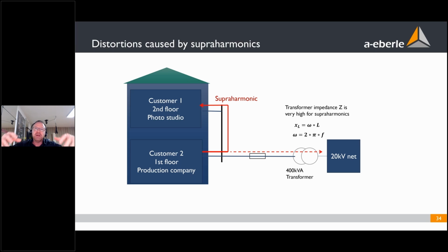And now this frequency is looking for a low impedance. The next low impedance it will find is in all the devices of the photo studio. Each single computer, switching power supply, and camera has a low impedance and gets a little bit of the current. And now the supraharmonic can go in a circle, so from phase and neutral to earth. So the supraharmonic we generate here wants to flow in a circle.